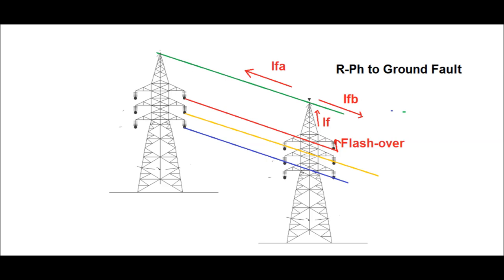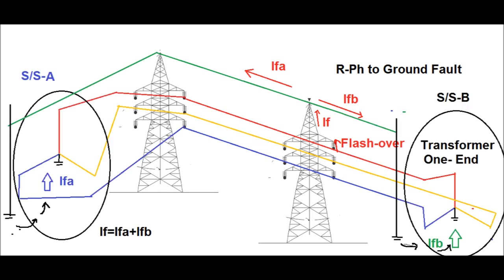For example, if a phase-to-ground fault occurs due to collapse of an insulator — for example, in the R-phase — then a zero sequence current flows from the R-phase to the tower body, and via the earth wire the current will flow to the nearby substation. Thereby it provides the return path for any phase-to-earth or phase-to-ground fault.